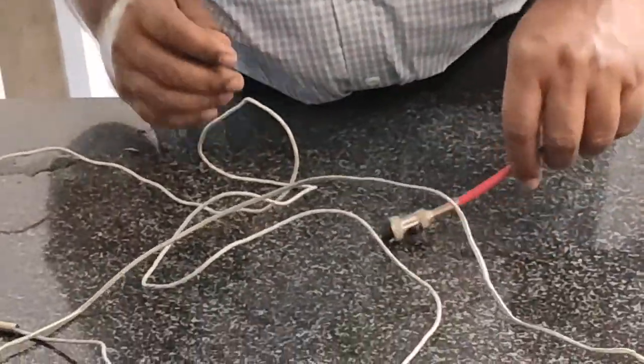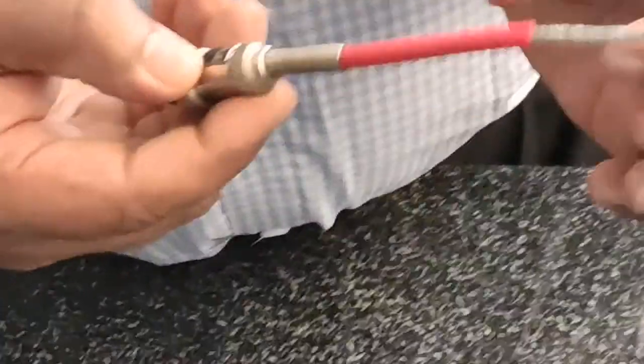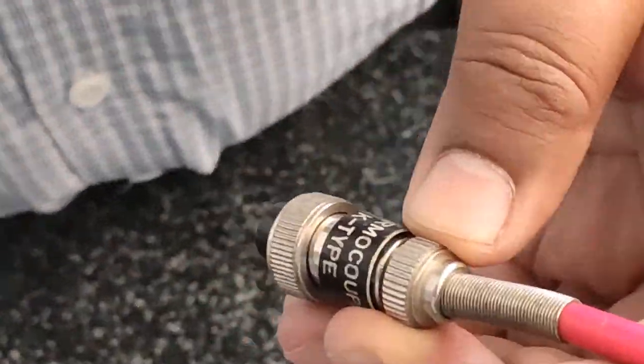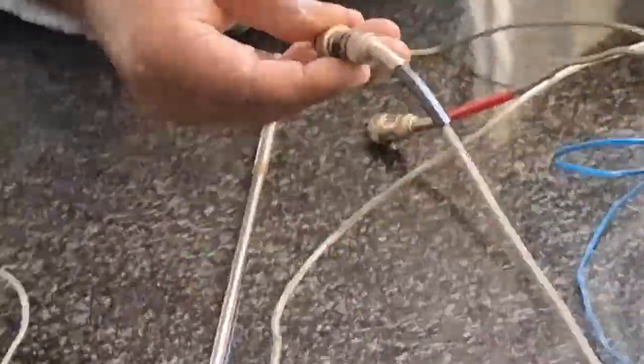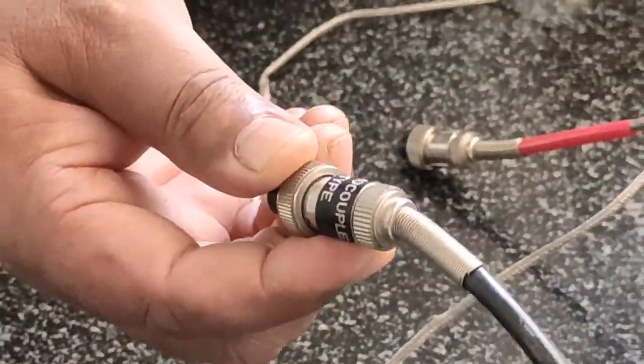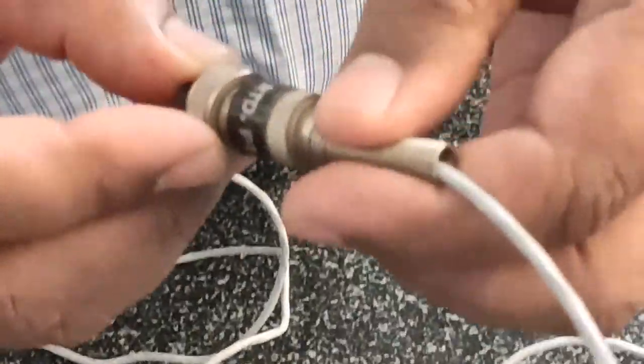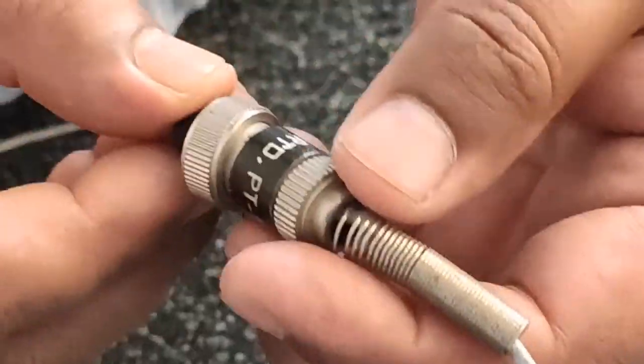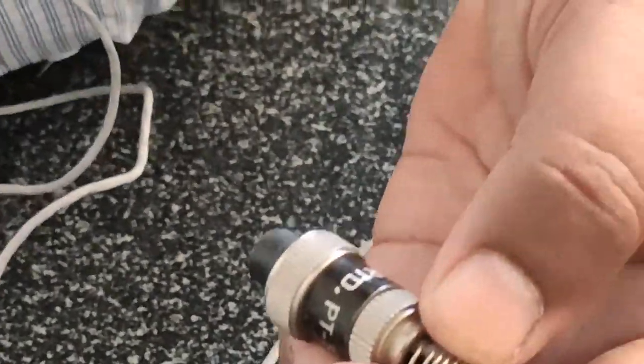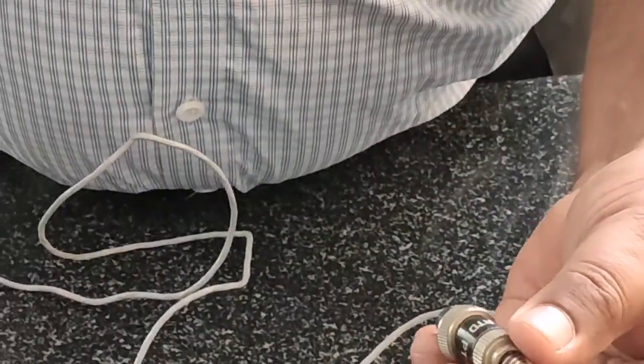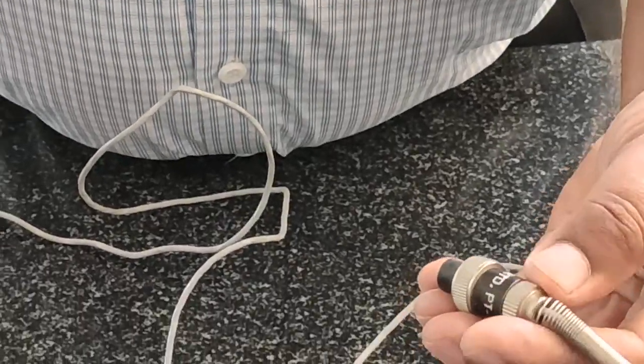In the same fashion we have another type of thermocouple with the red coding. This type is called the K-type thermocouple. These are the different types of thermocouples we use for measuring the temperature in the process. We have one more, the J-type probe. Among all these, we have the standard, what we call the RTD. This is the standard we prefer for calibrating all these types of thermocouples. It is called the resistance temperature detector.